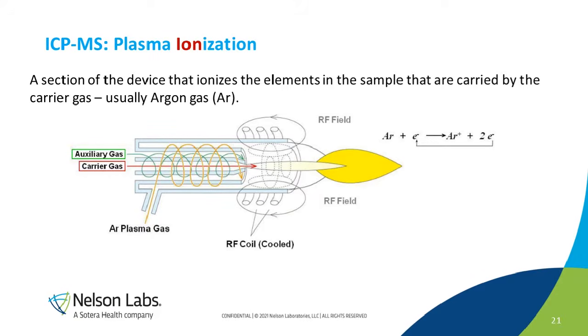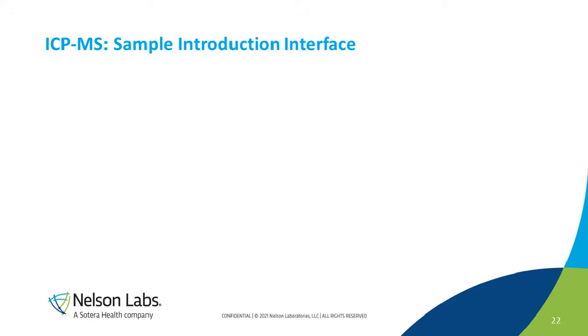So then it is saying the plasma torch turns it into plasma. So this diagram is actually showing how this plasma ionization occurs. A section of this device ionizes the elements in the sample that are carried by the carrier gas. We already mentioned before that usually we use argon gas. So here, obviously argon is going to lose this electron, so it is going to be positively charged.